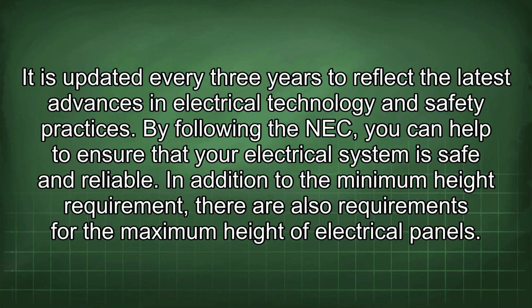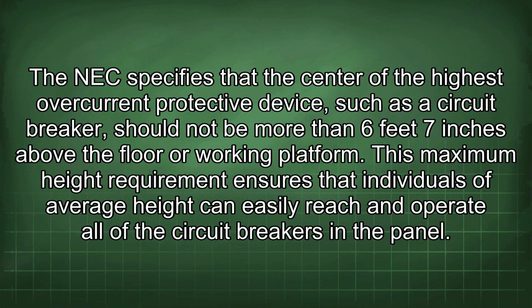In addition to the minimum height requirement, there are also requirements for the maximum height of electrical panels. The NEC specifies that the center of the highest overcurrent protective device, such as a circuit breaker, should not be more than 6 feet 7 inches above the floor or working platform. This maximum height requirement ensures that individuals of average height can easily reach and operate all of the circuit breakers in the panel.